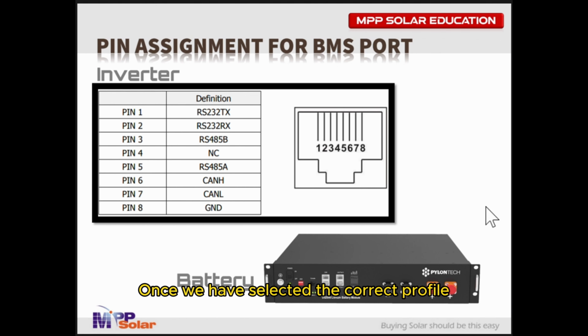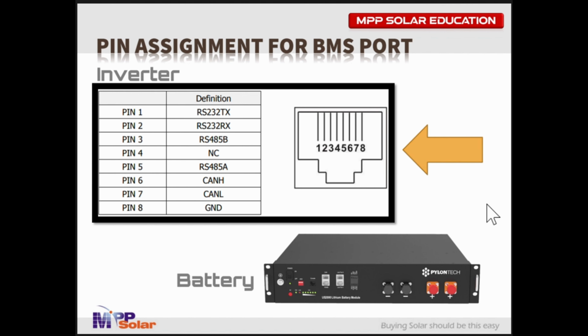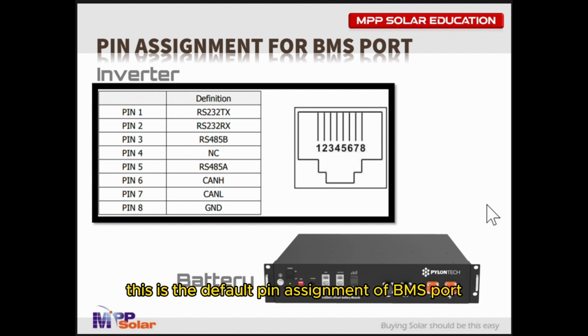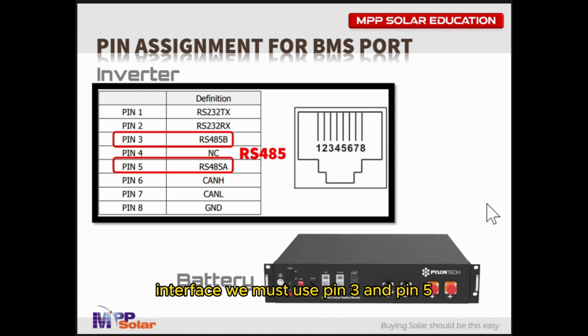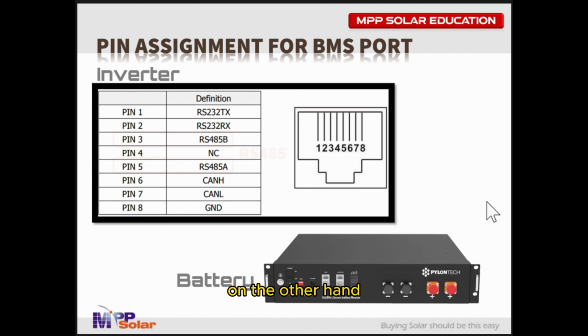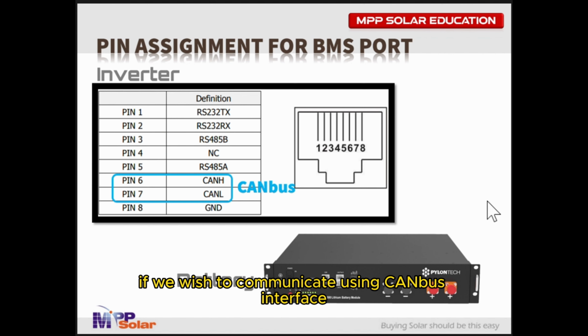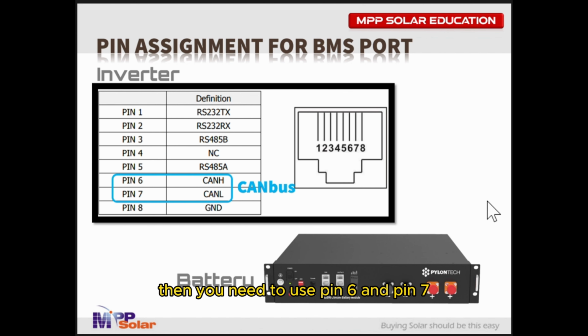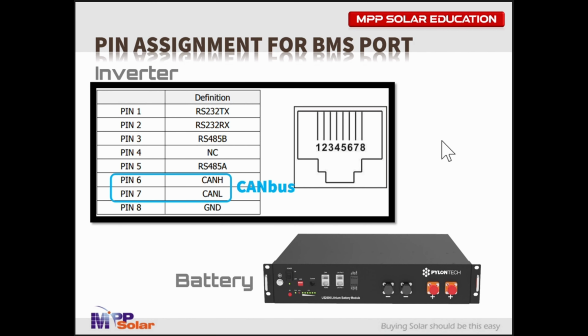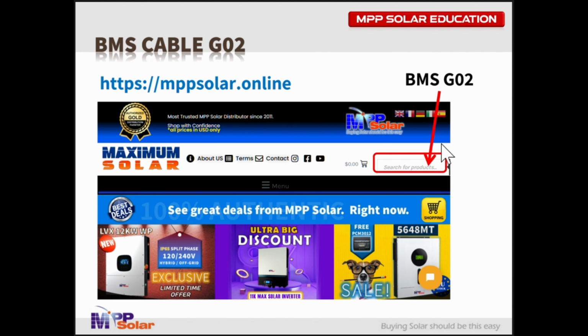Once we have selected the correct profile, we then need to make sure that we use a BMS cable with the right pinout, and this applies to both ends of the system. One end goes to the inverter and the other end goes to the battery. On the inverter side, this is the default pin assignment of the BMS port on an MPP Solar inverter. To communicate using the RS485 interface, we must use pin 3 and pin 5. On the other hand, if we wish to communicate using the CAN bus interface, then you need to use pin 6 and pin 7. On the battery side, you will need to check with the battery manufacturer and find out the correct pinout.